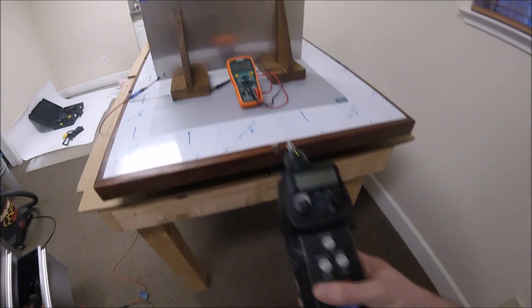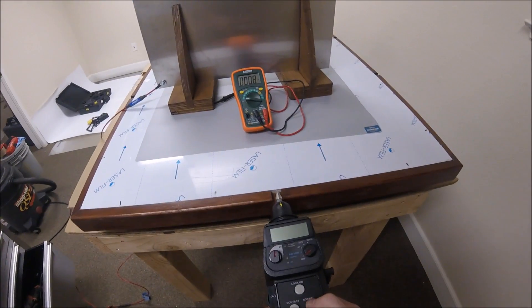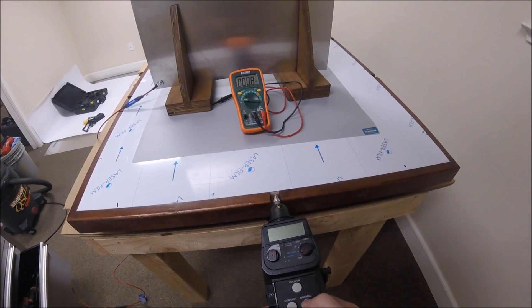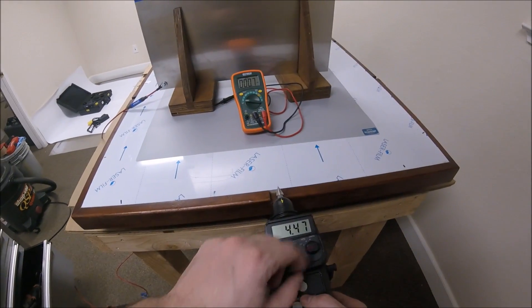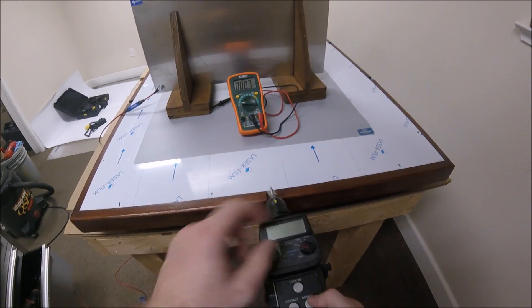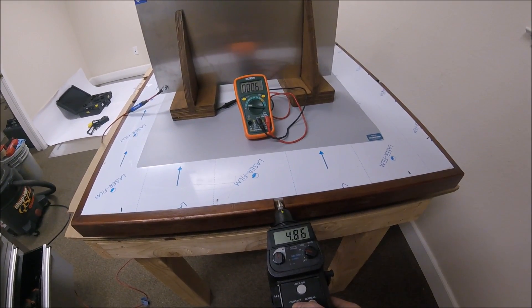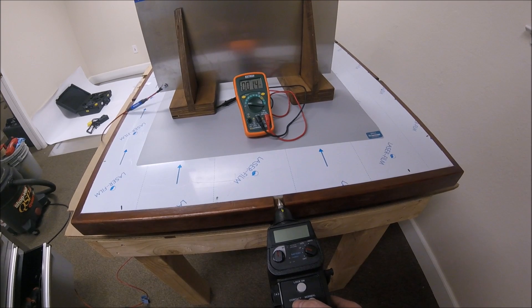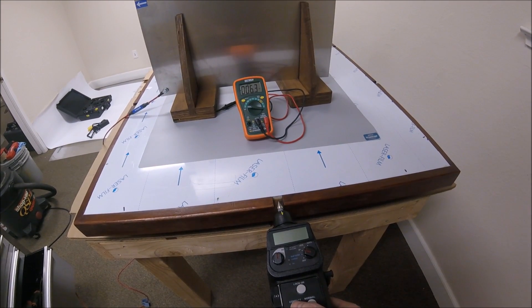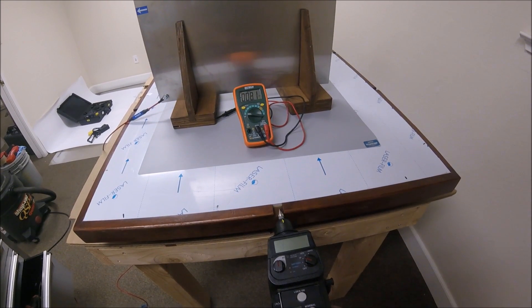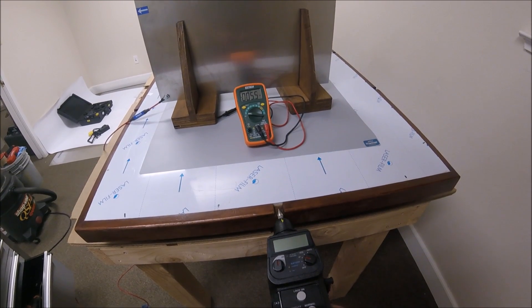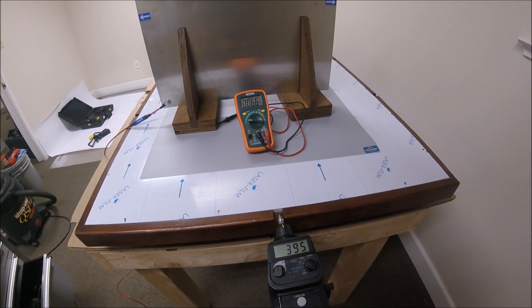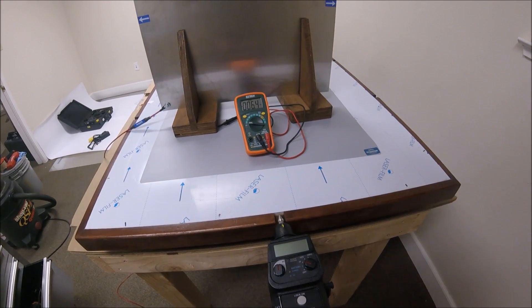With my contact tip in, I have the gun set to single shot setting, I'll manually apply discharges to the vertical, I'm sorry, horizontal coupling plane. This portion of the test seems less strenuous on the device, but have heard of failures occurring in this test method after passing the direct injection portion of the tests.